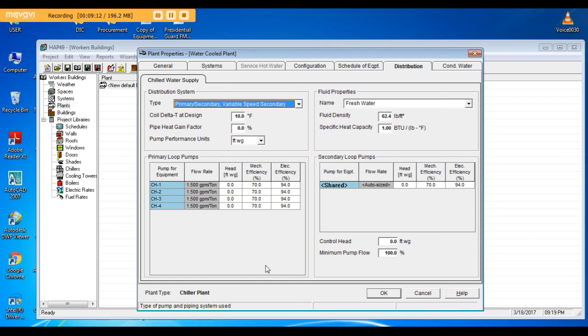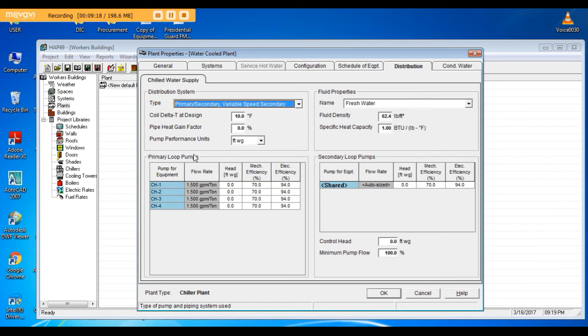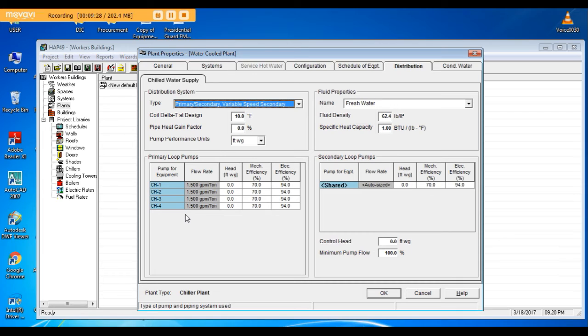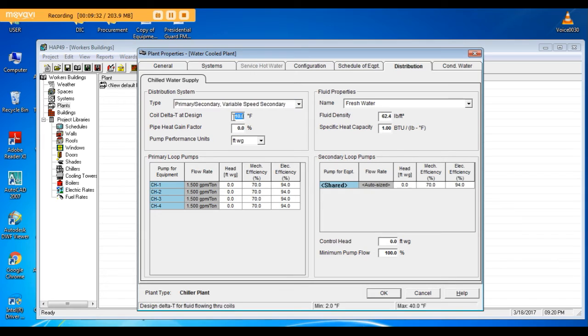Primary pumps will circulate water from the primary pump to the chiller to the secondary, and secondary pump will circulate water from secondary pump to external networks, buildings, and returning back to the primary pump. Coil delta T as we said 16 degrees Fahrenheit.